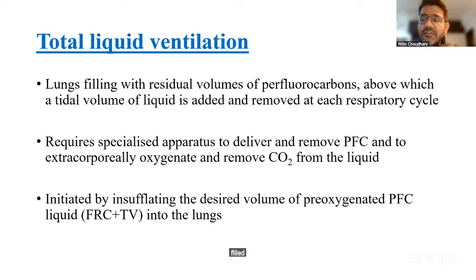So that's how it goes about. But it requires a specialized apparatus. The ventilators that we have are not designed to draw and deliver liquids. They are only for gases. So you require a specialized mechanical ventilator for that. And it is initiated by insufflating the desired volume of the pre-oxygenated perfluorocarbon liquid. That is, the tidal volume and the FRC is filled into the lung. And after that, you would start your ventilation with the liquids.